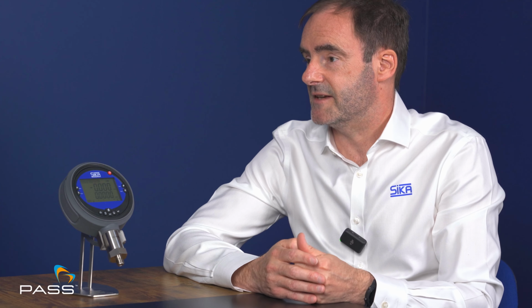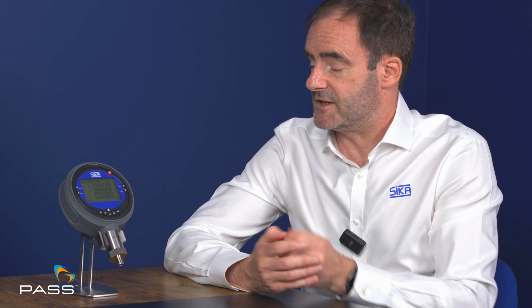So we can not only show the pressure of the actual gauge, but we can also show the pressure of the device we're actually calibrating on the same screen. All that data that we can see on the screen can be pulled out from the B2 and used as part of the calibration process. So it's data logging, this gauge? We can data log, yes, but we can also use all the data that's on the screen as a calibration certificate as well. So yes.